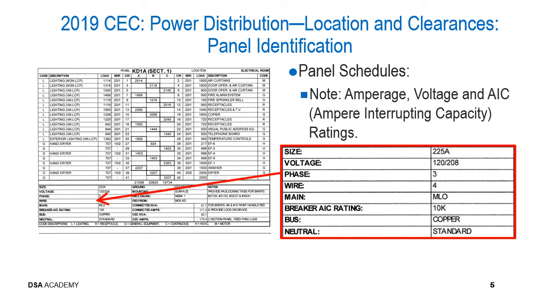Now it's important to understand that the ampere interrupting capacity actually describes the maximum fault current that a protective device, a circuit breaker or a fuse, etc., can clear safely without actually welding closed or causing damage to the equipment or to personnel. So we're going to see this AIC rating very frequently throughout this presentation, and you're certainly going to be wanting to pay particular attention to this number when you're reviewing materials that are being used on the job site. To continue, it's got a copper bus and a standard neutral. And again, these are just a few of the very important pieces of information that you're going to find on a panel schedule on the blueprints.